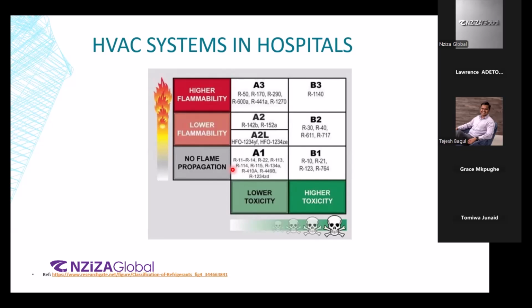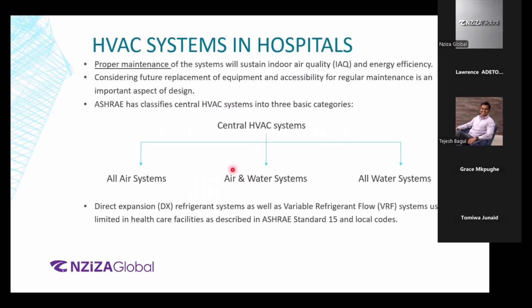So the reason I made sure that I have this last point separate from this one is because we need to make sure that in a given space, as we'll talk about in detail on one of the slides regarding the DX system, in a given space, again, we are talking about a volume, a maximum number of kgs of that refrigerant can be allowed if there is a leak. So if there might be 1 kg of refrigerant in this given space, a maximum of that much kg of refrigerant can be allowed to leak. If it goes above that, that might cause human hazard.